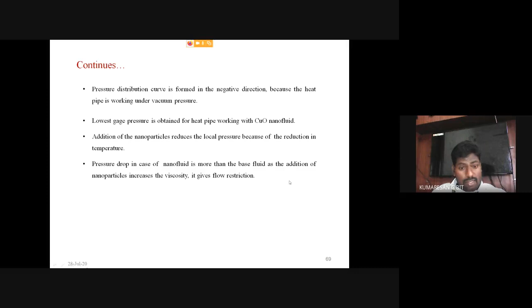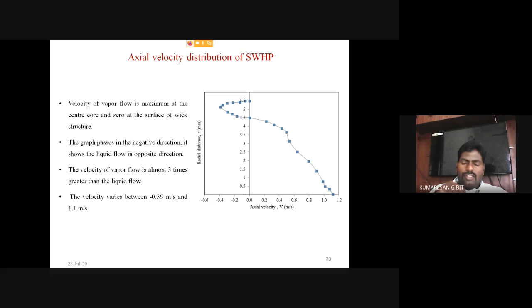Then axial velocity distribution of the sintered wick heat pipe. You see this is the axial velocity value, taken on the x-axis, then the radial distance is taken on the y-axis, and this is the starting point, and the radius of the heat pipe is about 6 mm. Okay, the diameter of the heat pipe is 12 mm, so only the radius is taken here. And you see here that the axial velocity is maximum at the center core area of the heat pipe, and it gradually reduces when it travels towards the surface area of the heat pipe. Okay, and even though the velocity is mentioned in the negative direction here, it indicates that the fluid flows from the condenser to the evaporator section by way of capillary action, that means by way of the wick structure.